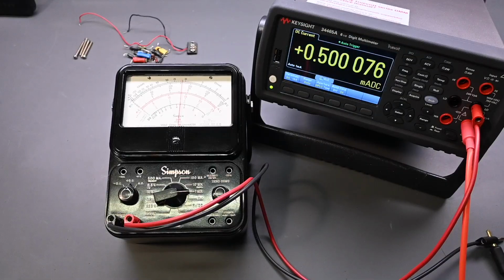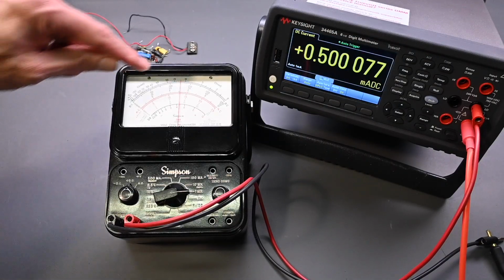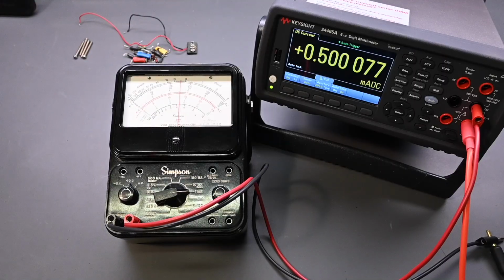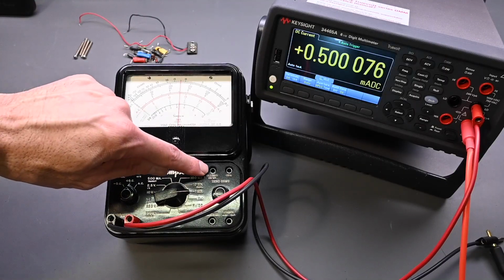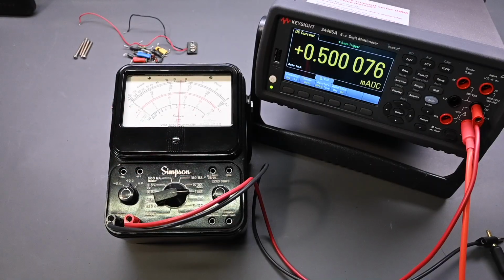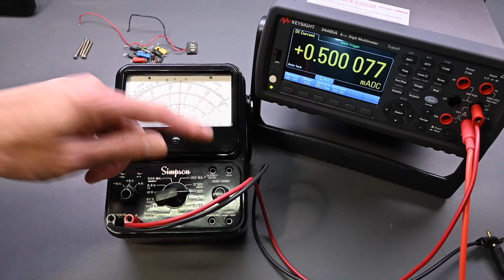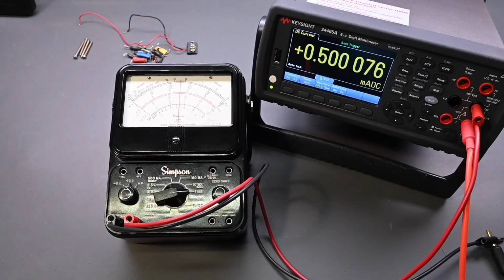There's 500 microamps, or half milliamp. Perfect. And we've already seen that this 50 microamp input is working correctly, because if it works on 250 millivolt input, it will also work on 50 microamps, and we saw that during the calibration. So the current ranges and the voltage ranges are spot on. So now let's take a look at the resistance ranges.